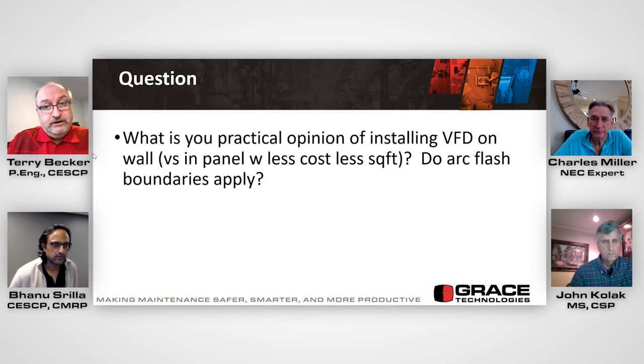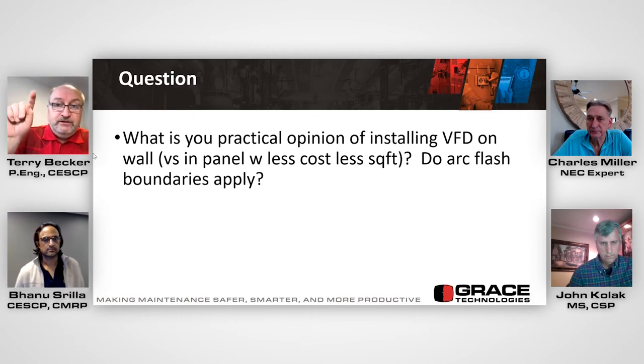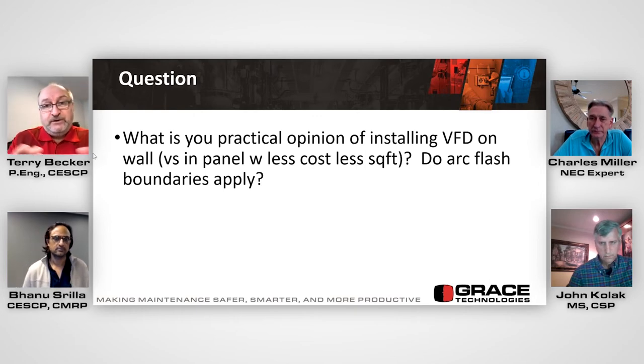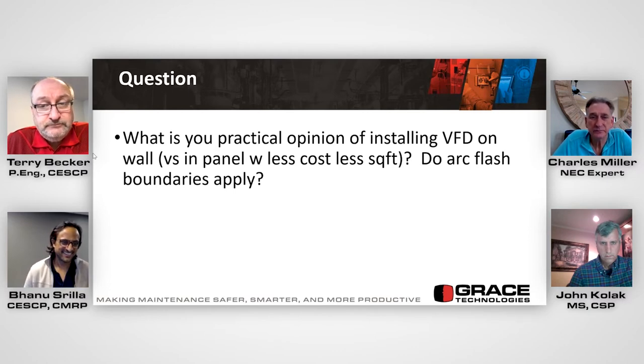So, long-winded question, it involves risk assessment, but we start by saying normal equipment conditions, and there's six parameters in 70E and Z462 that are valid, right? But you don't need PPE to walk in front of a drive or use the HMI on it. The arc flash boundary doesn't exist. Don't paint lines on the floor around wall-mounted VFDs or starters or panels. It's not valid. So what are your thoughts, John?